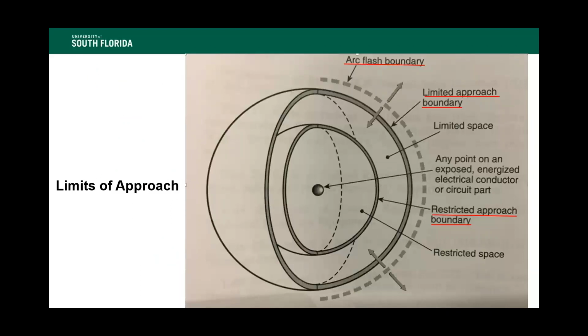Here we see a graphical representation of those boundaries. If you look at that center dot, that little globe on the interior of these two spheres, that's any point of an energized electrical source. It might be the end of a wire. If we come out to that first sphere from that point, that's the closest we can get for a qualified person, somebody who's trained to recognize and work with electrical hazards. That's really the closest they can get to it. When we talk about approach, it's actually working distance, at least in respect to this parameter. The working distance is the distance from the energized source to the face or chest of the person who's approaching it.